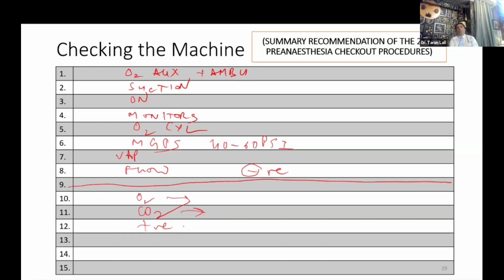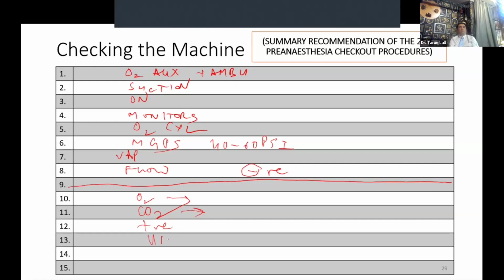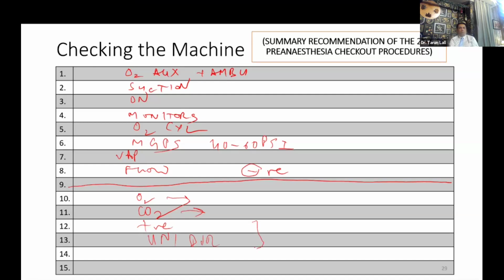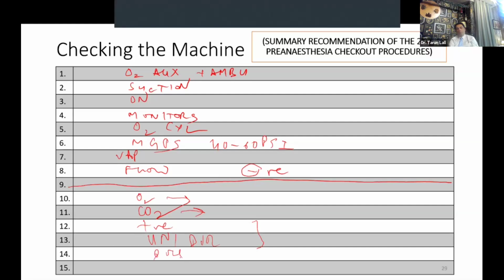So once we have done the positive pressure test, then you come and check the unidirectional valves. So after oxygen and carbon dioxide, the next pair is your positive pressure test and your unidirectional valves. Your exhalation valve and your inspiratory valve, you see that both of them are functioning properly. When you press the bag, the inspiratory valve moves up, and when you release the pressure on the bag, the expiratory valve should show motion. And finally, you do the documentation and you come to ventilator settings for the current patient. So this is how we test the machine and we declare that I am ready.